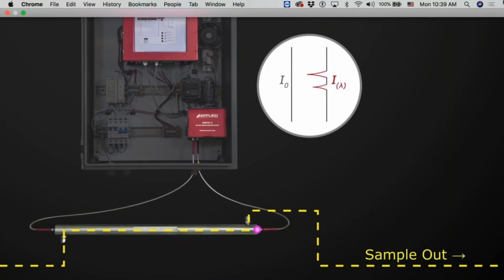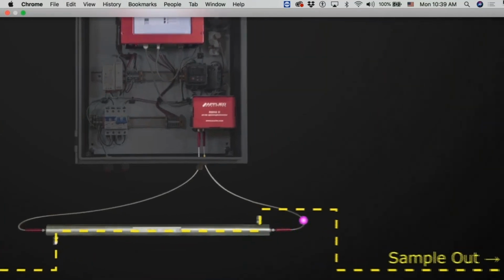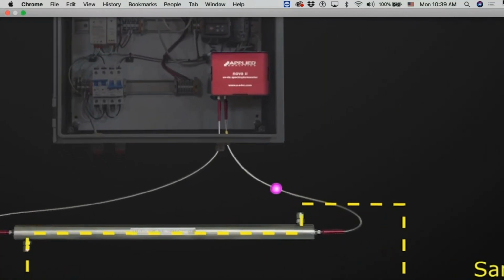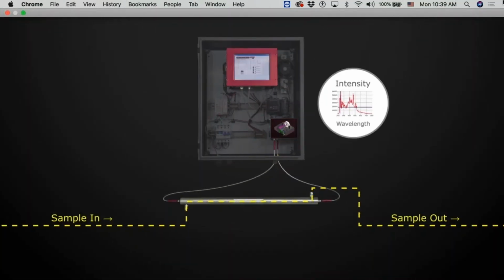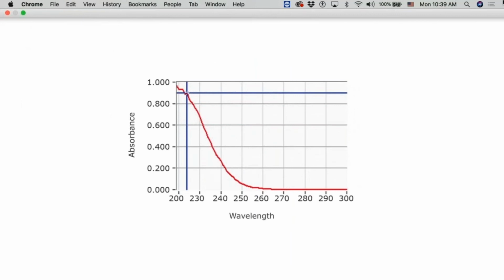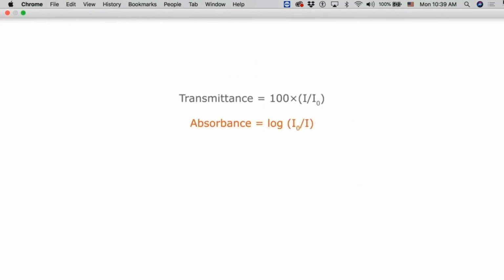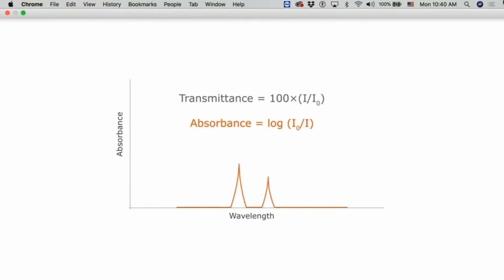Now containing the distinct absorbance imprint of desired chemical components, the signal exits the flow cell on the opposite end through a collimator and travels via a fiber-optic cable back to the spectrometer inside of the analyzer enclosure. The light intensity spectrum measured by the detector is processed by the analyzer's HMI unit.